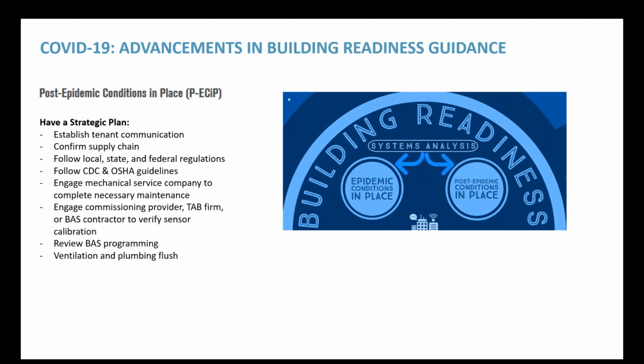To review any of the BAS programming that may have been altered during epidemic conditions, that needs to be reverted or changed in some way to allow occupants to come into the building. And then finally, there's the ventilation and the plumbing flush. Once you know that everything is in working order, it needs to be turned on and operate for some period of time, typically days, to make sure that everything's working correctly, that you're flushing air through the building, and removing any contaminants that may be in there.